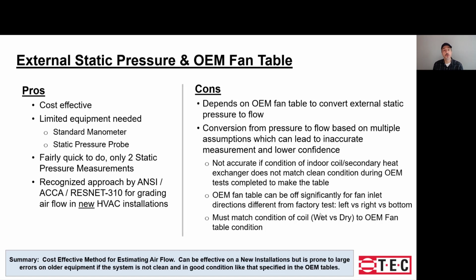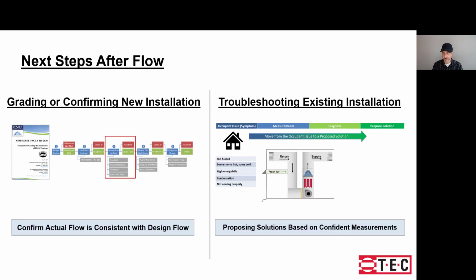The cons are you're using that OEM manufacturer's table to convert pressure to flow. And so if you're not matching the exact conditions that were present when the OEM developed that table, then you have some uncertainty. It can lead to poor measurements and more limited confidence in your measurements. And so while it's recognized for grading new installations, if you're going into an existing installation and trying to verify the flow as part of troubleshooting or confirming equipment, then you're going to have less confidence in these readings, because a dirty blower or a dirty coil can really impact the readings you're going to get.